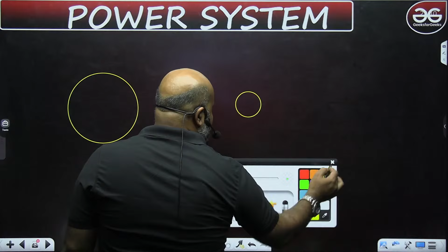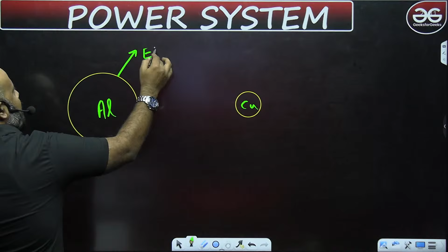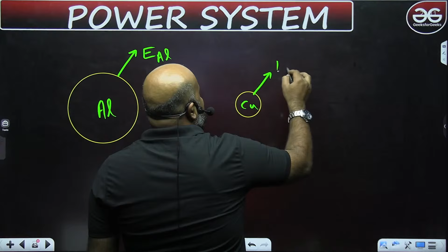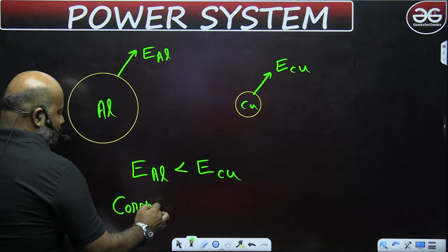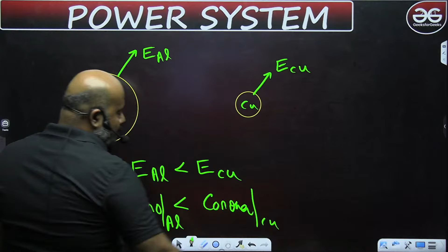Now the aluminium conductor's cross-sectional area is large, which means the electric field stress is going to be comparatively less in case of the aluminum conductor compared to the copper conductor. So in this case, corona is going to be less in case of aluminium compared to the copper conductor.